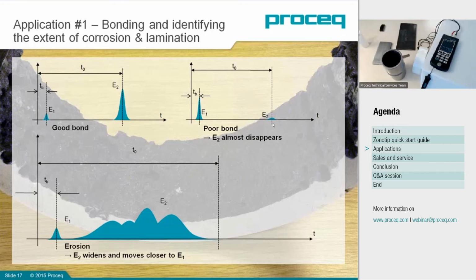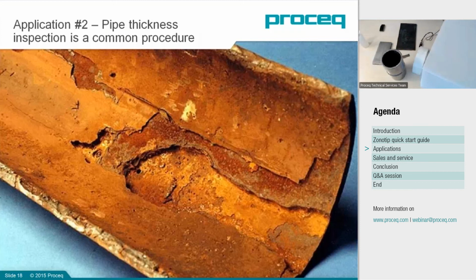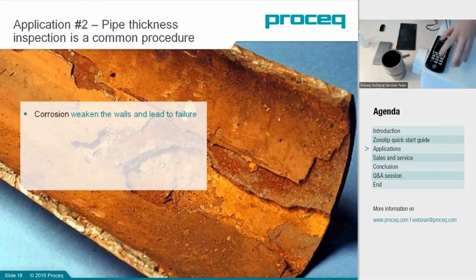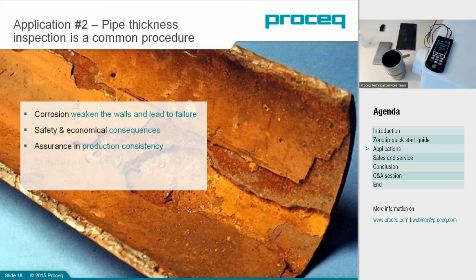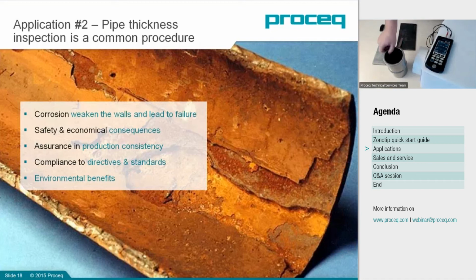What Chris is going to show you now is a very straightforward standard application for Zonotip, which is the true thickness measurement and how easy it is to perform. Sure, thanks Ali. I've already zeroed and calibrated the device. We used the stepper block, it's steel. What I'm going to test is the thickness of this pipe here. This is a common application for manufacturing, for example, where you need to verify that the thickness of the pipe is to standard and to specification within tolerances.